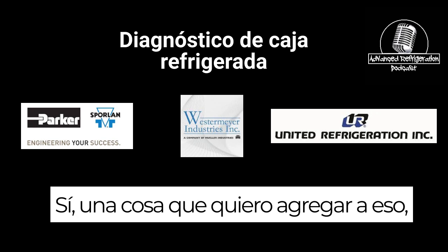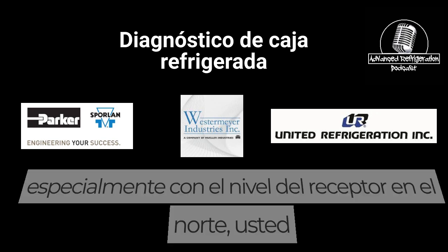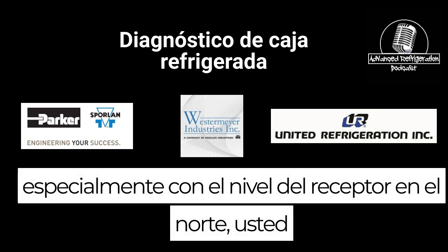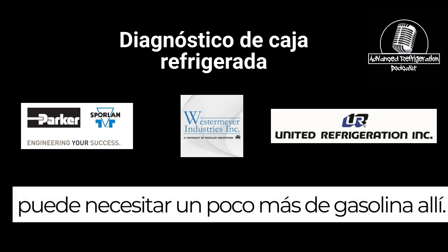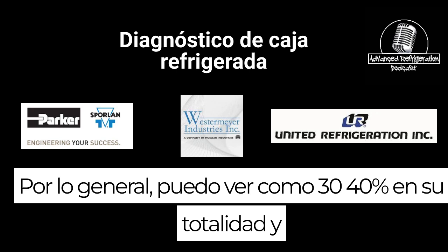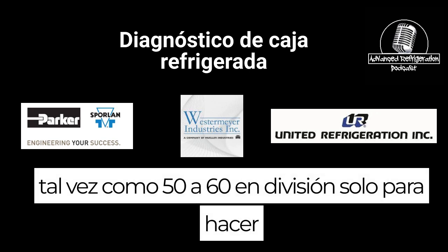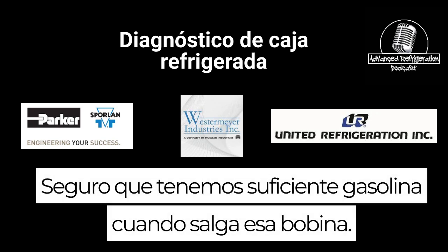One thing I want to add to that, especially with the receiver levels, being up north, you may need a little bit more gas in there. So typically I can see like 30, 40% in full and maybe like 50 to 60 in split, just to make sure we have enough gas for when that coil comes out.